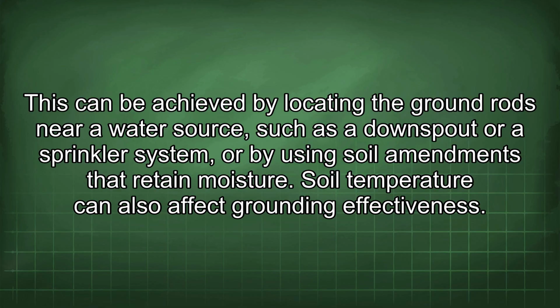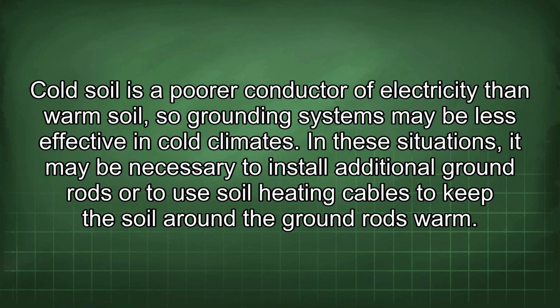Soil temperature can also affect grounding effectiveness. Cold soil is a poorer conductor of electricity than warm soil, so grounding systems may be less effective in cold climates. In these situations, it may be necessary to install additional ground rods or to use soil heating cables to keep the soil around the ground rods warm.